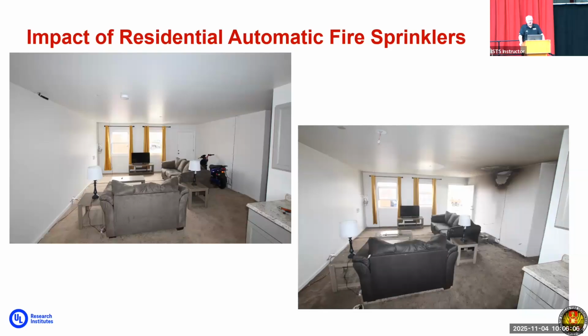In this particular case, the amount of energy that was released so fast from the scooter triggered 4 sprinkler heads. One of the things with the NFPA 13D system is they're only designed to flow 2 sprinkler heads. So we were pleasantly surprised to see that even though the sprinkler closest to the scooter had a reduced flow rate of about 9 gallons per minute, it was still enough to wet the furniture and prevent fire spread.